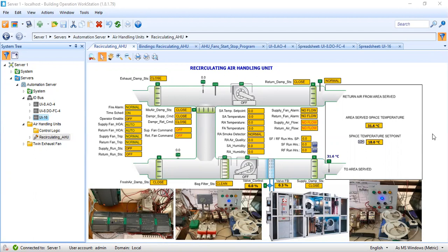So in order to cool this area, we need to allow more chilled water to go inside the cooling coil. Now the chilled water is being produced by chillers. Chillers will be the ones to produce the chilled water supply for all the air handling units. Now the chilled water supply is around 5 degrees. Then we are expecting a delta T of maybe 6 degrees, then the return temperature to the chiller is around 11 degrees. So the more chilled water entering the cooling coil, the more chances that the air being supplied will cool down.